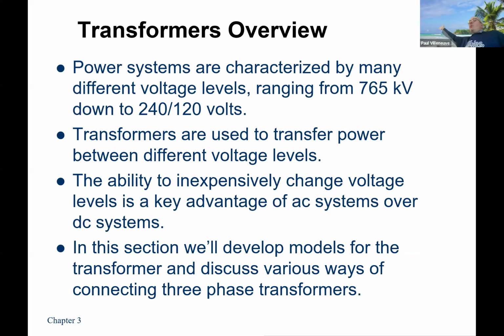So you can work up to 765 kV or down to 120 or even lower. It really depends on what you want. If anybody here has an older doorbell system, you don't have the Ring stuff, right? If you have the old push button, you hear the ding dong, and it's not wireless. If it's hardwired, you most likely have a very small transformer that steps that house voltage down to around 24 volts AC, typically. But going into our house, there's a transformer with 100% certainty. There's a transformer that steps it down to 240 volts, at least here in North America. And then we have the 120 again for the center tap. So we'll look at that in more detail.